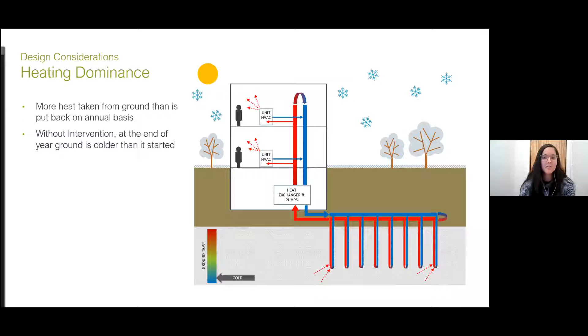Possible interventions to help mitigate heating dominance would be to connect a domestic hot water boiler, or to connect a supplemental boiler to your heat exchanger to help bump up the loop temperature and supplement heat to the units.